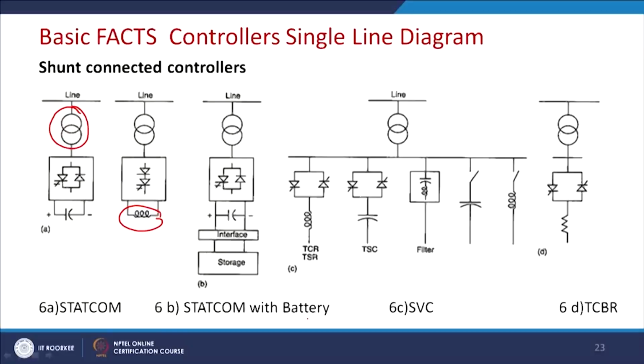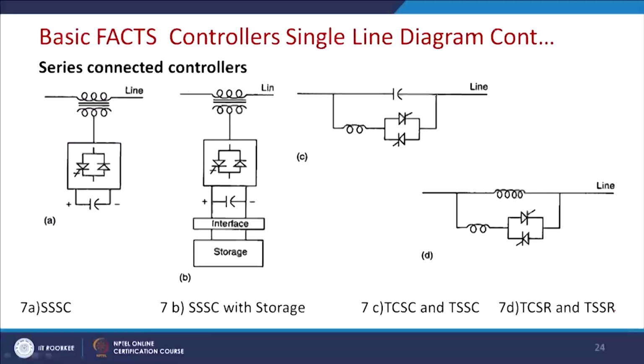And now let us come to the figure of the SVC, static VAR compensator. The static VAR compensator consists of a family of FACTS devices and power quality devices. So this is actually the TCR, this is the TSC, thereafter you may have a line filter, then an uncompensated capacitor, an uncompensated inductor, and this is actually the TCBR. This stands for actively damping the circuit. Now let us consider the FACTS device which is basically the SSSC. It is a series controller. Again it is the same as a STATCOM, but it requires a series injection, and it can also have a current source converter topology, but that is not very popular. For this reason, voltage source converter topology has been shown here.